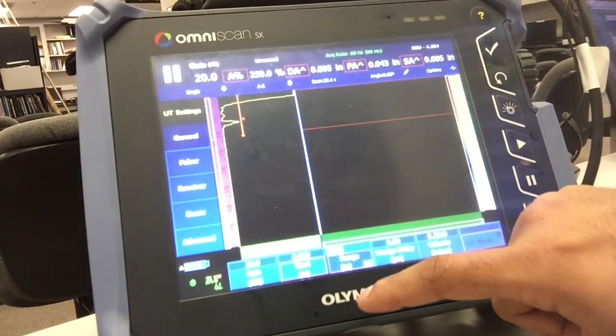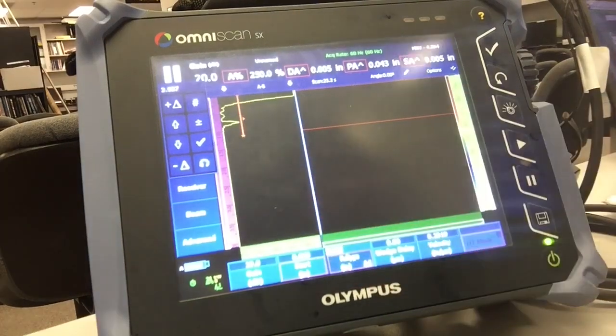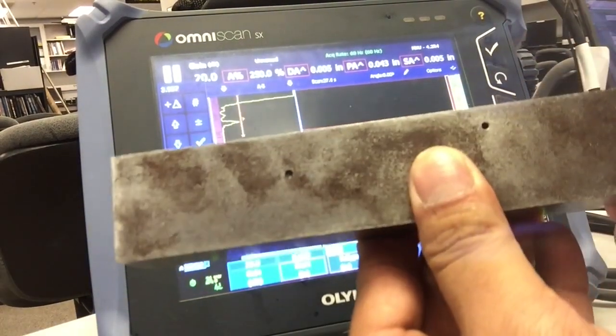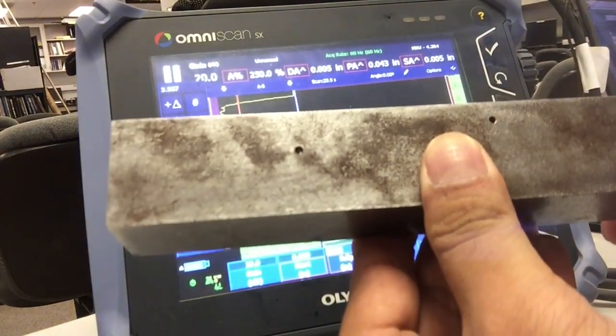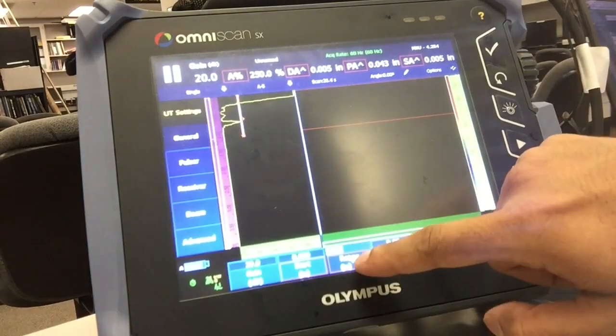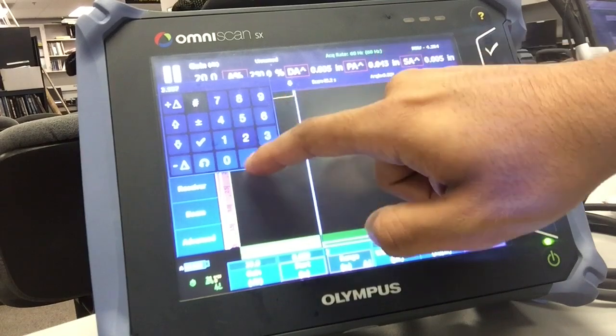I want to keep my range to twice the thickness that I'm going to calibrate off of. So in this case, it's 1.25 inch. So I'm going to keep my range about 2.5, 2.6 inches.